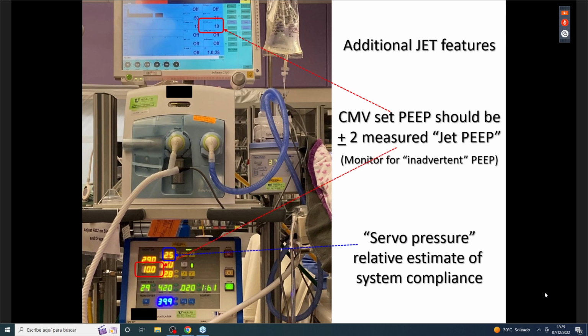When coupled with this standard ventilator, the set PEEP, as shown on the ventilator here, is currently 10, which is what's set to be delivered to the baby, but the jet actually measures its own PEEP. Significant differences between the measured PEEP on the jet and the set PEEP on the conventional ventilator can be used to assess for inadvertent PEEP. So if this starts to creep up to 2 or 3 centimeters above this setting, you need to think that maybe you're air trapping and you need to reinvestigate the settings that you may be using.